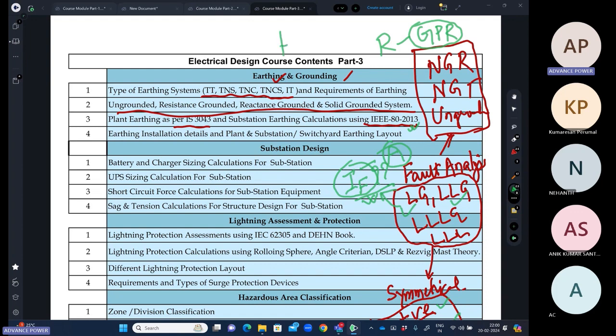When I am talking about the human body, IEEE elaborates in very much detail. They started with experimentation, which was also done on human beings. They gave currents to animals first, like rat, pig, cow, and then to humans. They decided the sensitivity to the amperes of current and, based on that, derived empirical formulas for a 50 kg human body and a 70 kg human body. They defined what the human body can tolerate when there is a lightning strike or a fault in the substation.